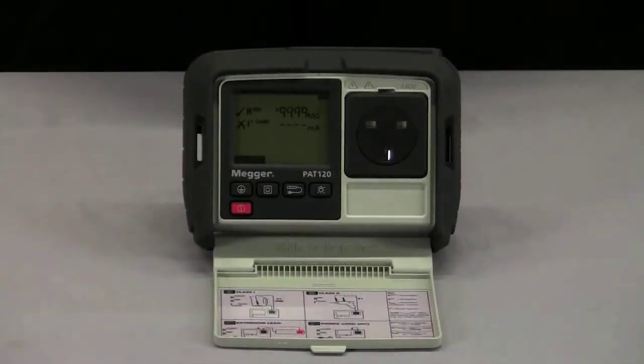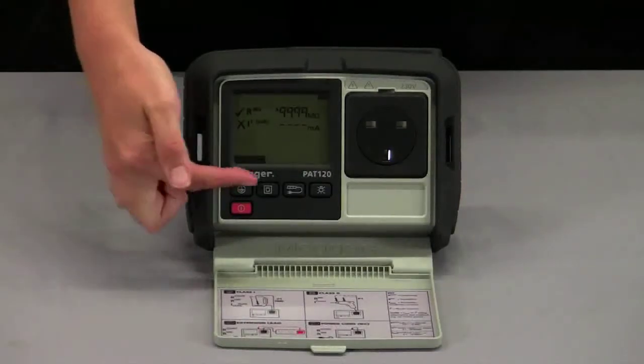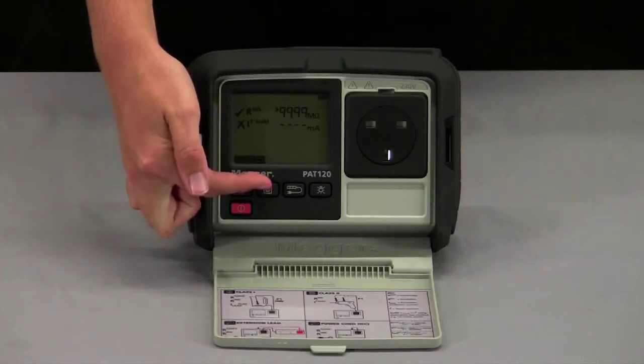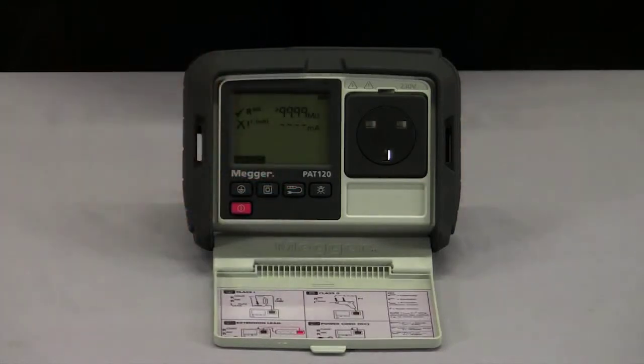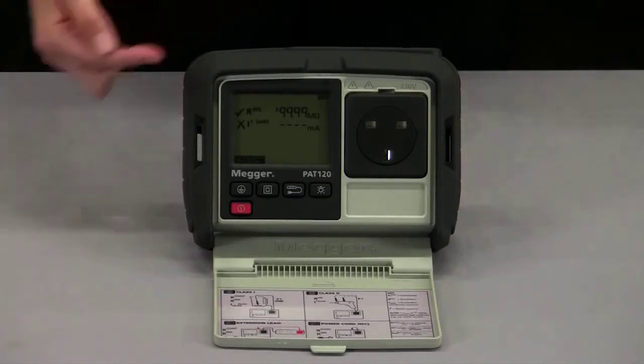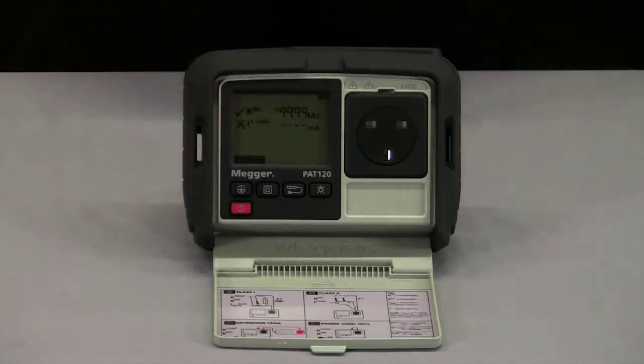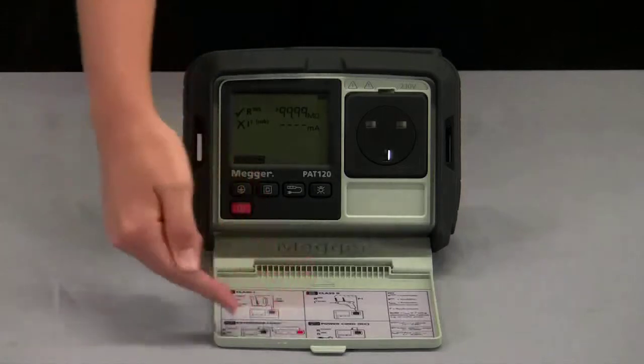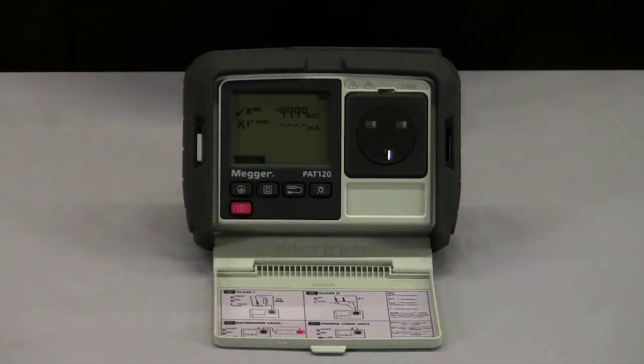The PAT120 is a simple to use handheld PAT tester that will lead you through testing Class 1 earthed equipment, Class 2 double insulated equipment and extension leads. There are preset limits in the PAT tester that will indicate a pass or fail with a tick or a cross. The connections are all shown in the lid. In addition, there are test certificate templates provided on the support document CD.